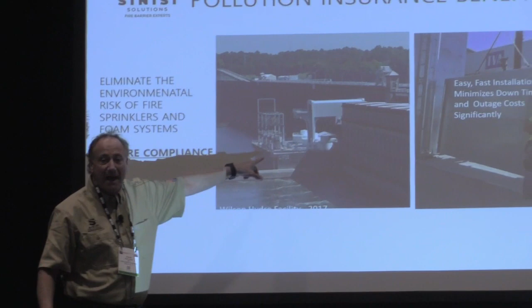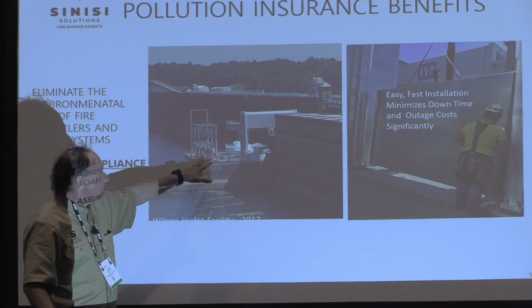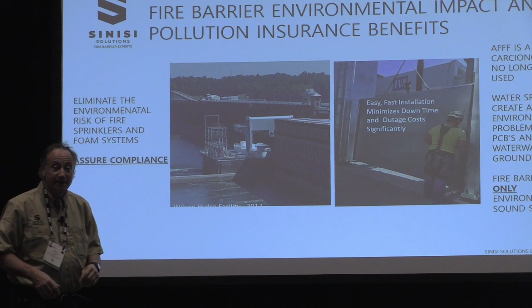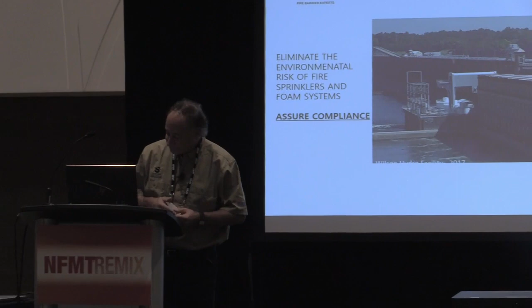The second method, which is the most common, is the water sprinkler deluge system. Environmental nightmare. PCBs, oil, thousands and thousands of gallons of water, and it doesn't even put the fire out. It's a transformer, it's a hydrocarbon fire. You're wasting your time. This system here is on the Wilson Hydro Dam, provides most of the power to Alabama. Those couple transformers, if they were to fail with the sprinkler system, you'd have a river full of hydrocarbons. You can comply with NFPA, with fire code compliance, with safety compliance, environmentally sound with separation and compartments.